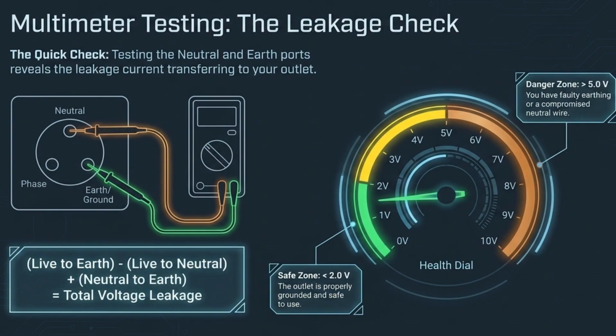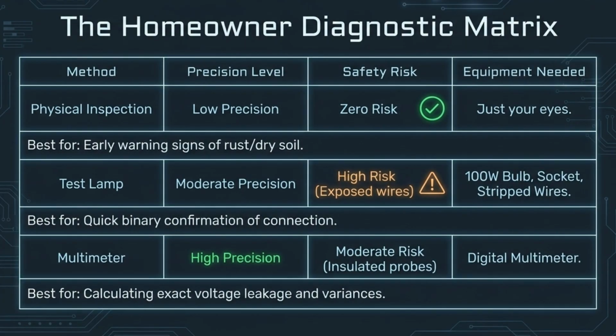You can also perform a leakage check by testing between neutral and earth. A reading below 2 volts is generally safe, while anything over 5 volts indicates a problem with your earthing or a compromised neutral wire. This diagnostic matrix summarizes the methods we have discussed. While visual inspections carry 0 risk, using a test lamp or multimeter involves dealing with live electricity, so always exercise extreme caution during your testing.